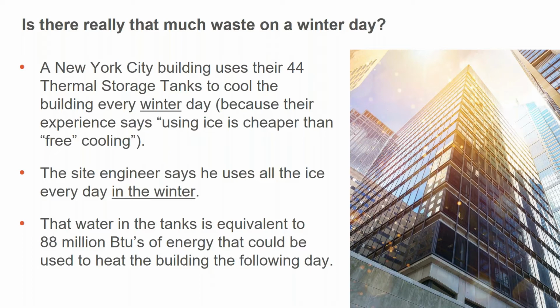And I asked them why, and they said, well, it's cheaper actually. And I'm like, really? And they say, yeah. And so they went into the analysis of when you're running free cooling, you got a lot of cooling tower fans running, and you've got major pumps running, and all that's running on peak. Whereas when you charge up the ice tank, it's running at very high efficiencies at nighttime on a colder winter night, and it's all off-peak energy. So they've made the case it's cheaper. So that's why they're doing it.